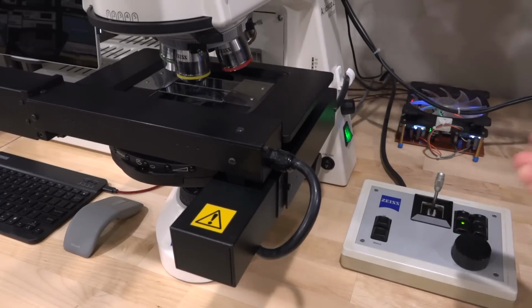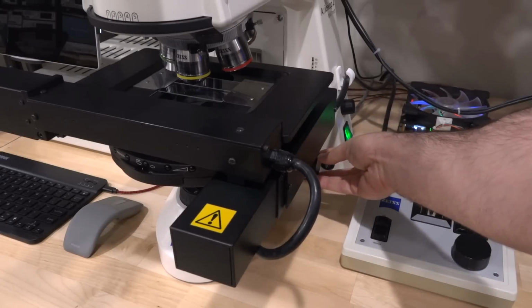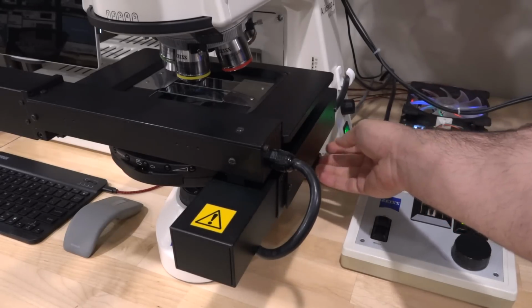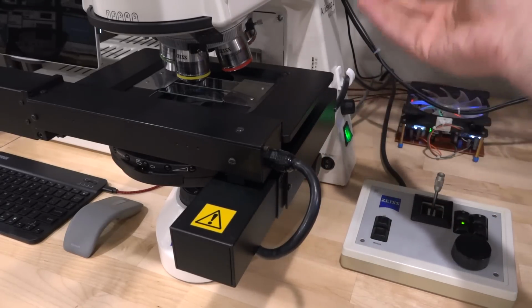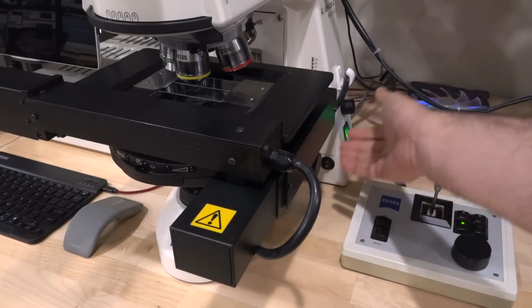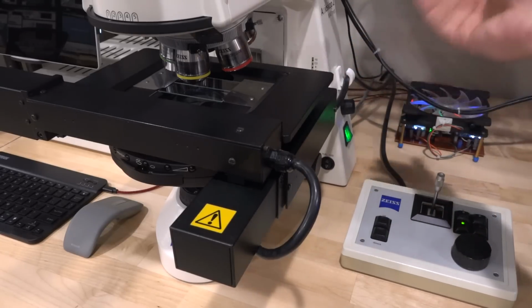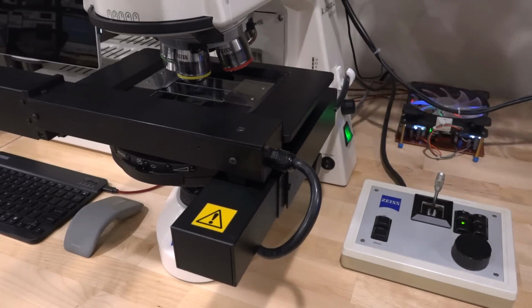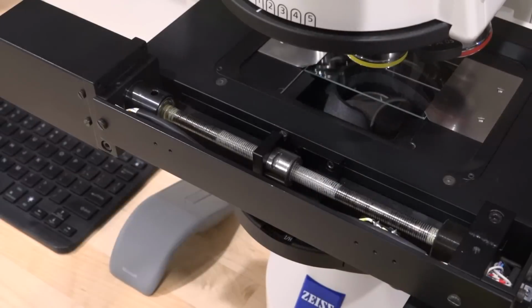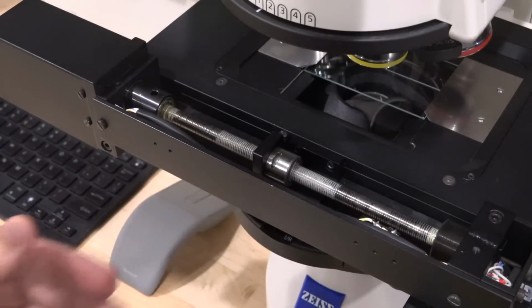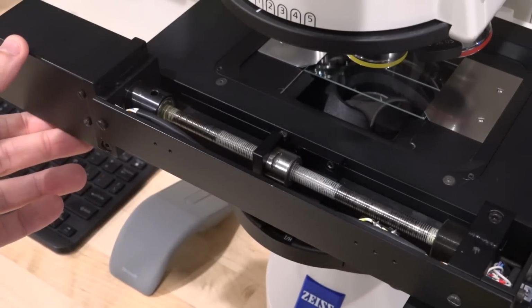And the Z movement itself is also motorized, and you can move this. So when you move this knob down here, you're actually not moving it mechanically by gear connections. You're sending encoder pulses to the controller, and the controller moves this using a servo as well. So this basically now has XYZ servos. So here's the structure of the X movement, which is the same as the Y movement. This is just easier to show you this one.